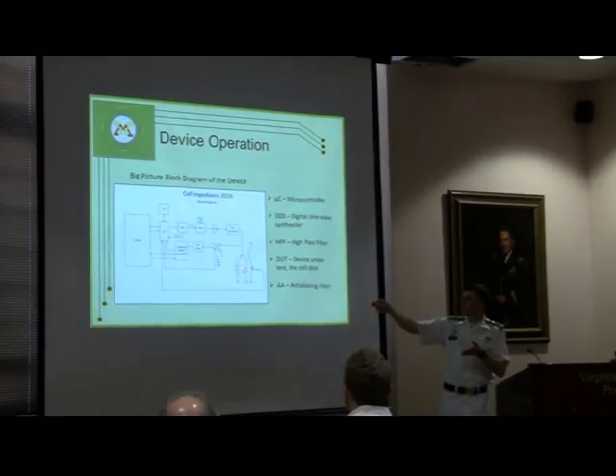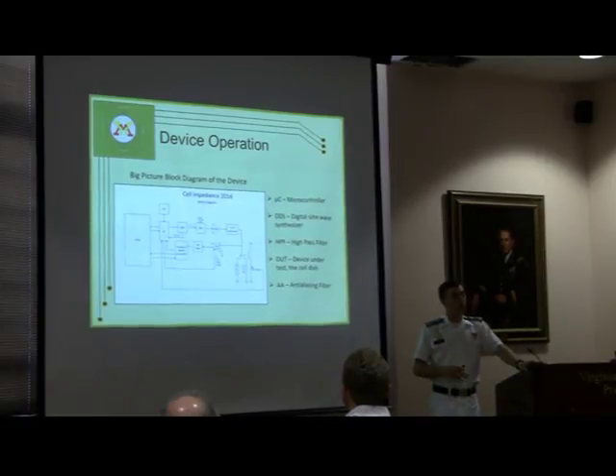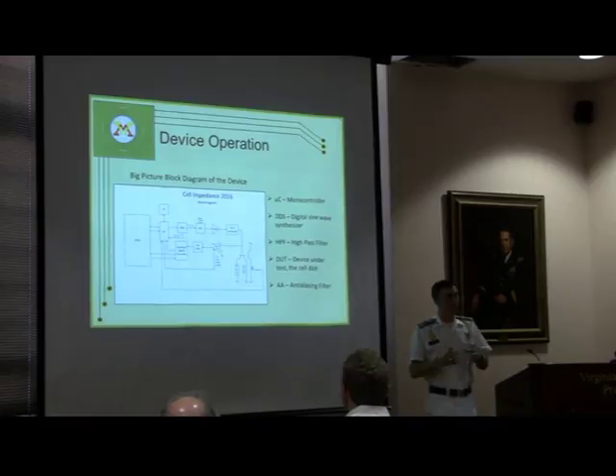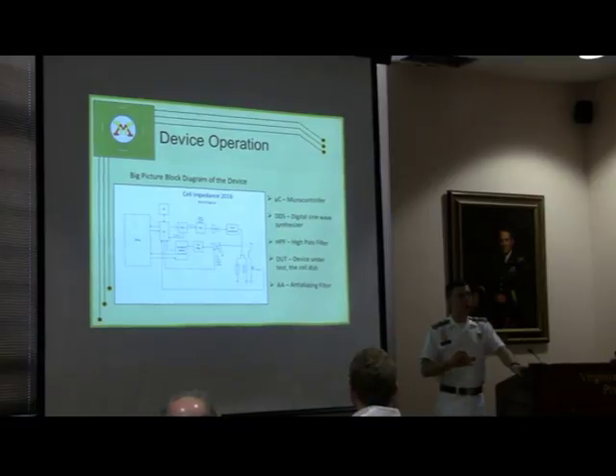And what we have the testing capacitor in here, this calibration capacitor, or a calibration resistor as it was, is to give basically a set of data. So when you start the experiment, it goes through a calibration routine first. So any kind of data that it's going to get from the actual experiment, it's going to run all that through the calibration resistor first. And what that allows it to do is it allows it to basically find any errors in the waveform, any offsets, and correct them all, so that when you're getting the actual data, everything is calibrated so that you're running the same thing every time, and there's no deviation that could throw off your experiment results.